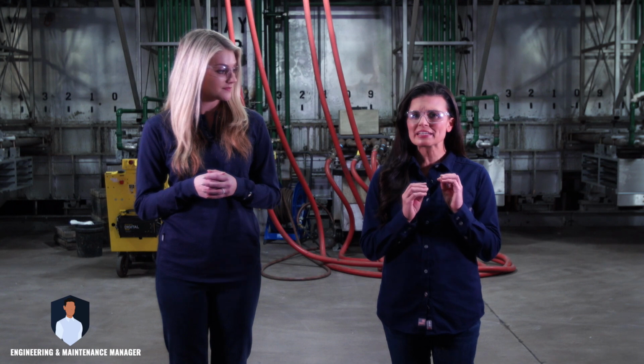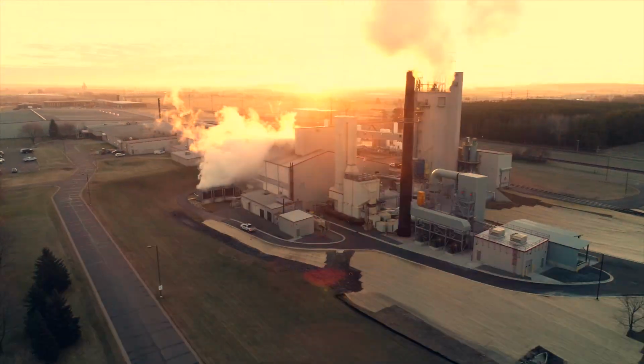Take breakers and switches as an example. Some have been in the closed position for years, and that puts us at greater risk of an arc flash event when we open them. Breaker trip settings also play a major role in arc flash study calculations. If your breakers aren't tested and operating to the correct specs, it will affect your calculations, and that could cause a serious problem for someone working downstream who might be underprepared for an arcing event.